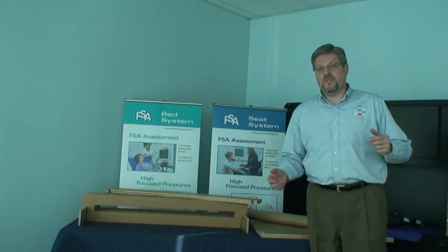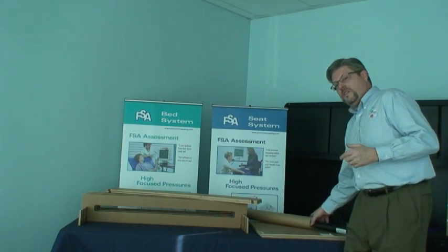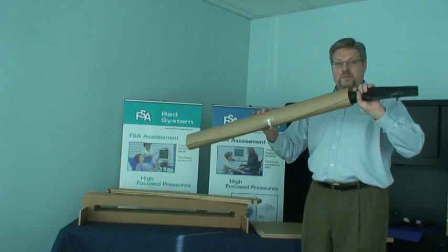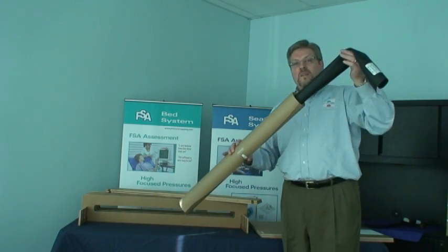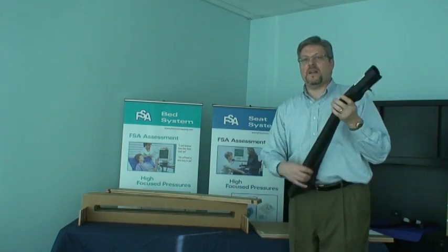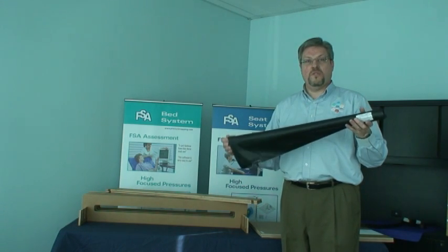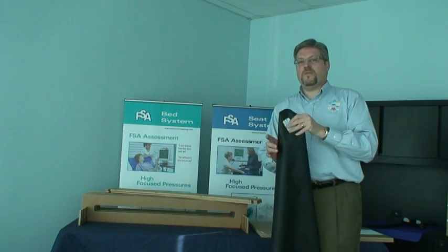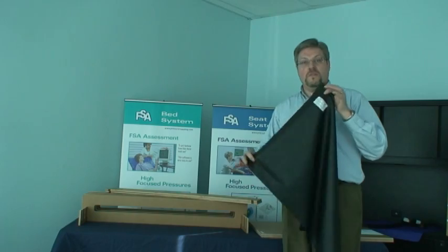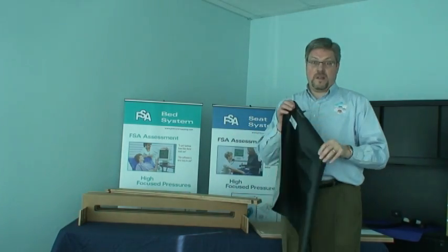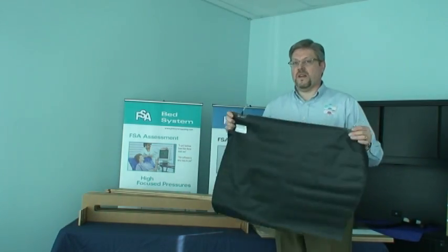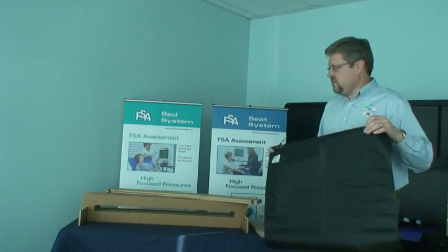One of the most important things to remember when you're unpacking the calibration jig is to check inside all the shipping material. We often get a call with people looking for components and they're actually packed very carefully inside those cardboard tubes. And if you mistake it for shipping material and throw it out, you've just thrown out your inflator or perhaps your sphygmomanometer or your pump. So check inside all the packing materials before you dispose of them.